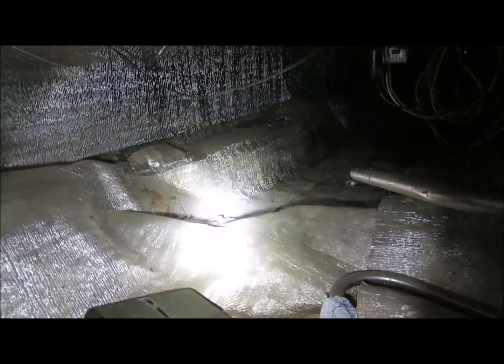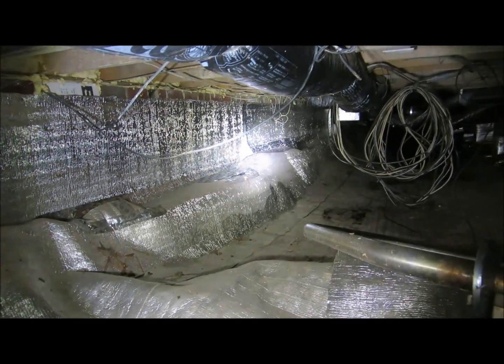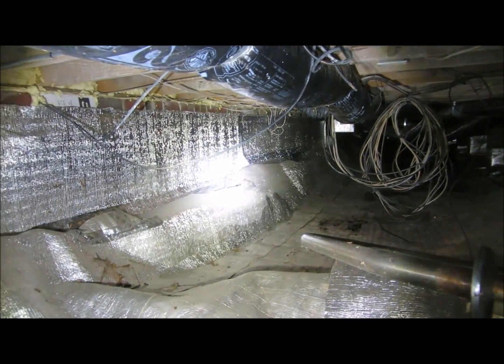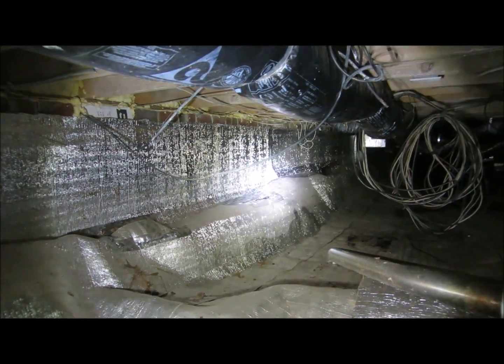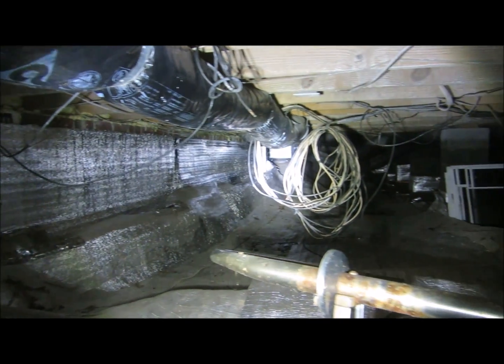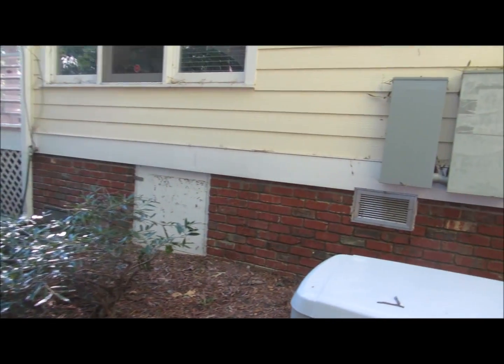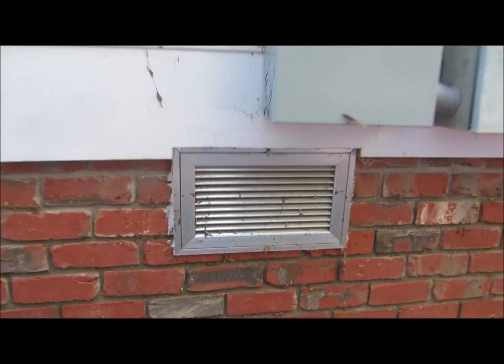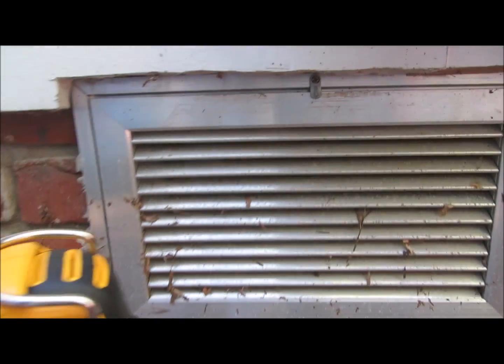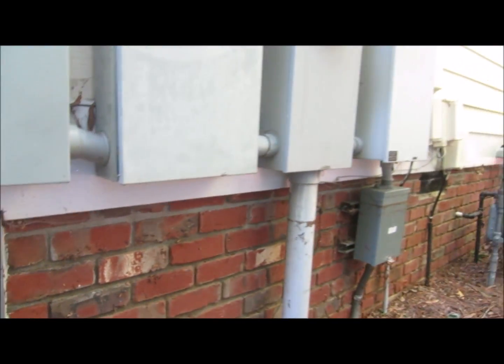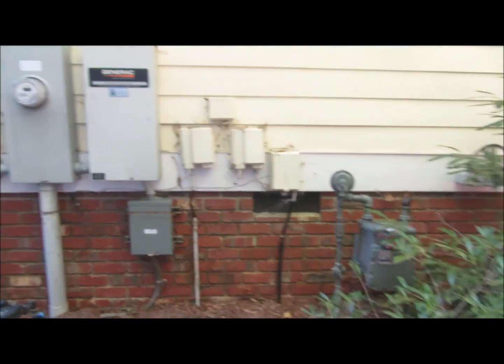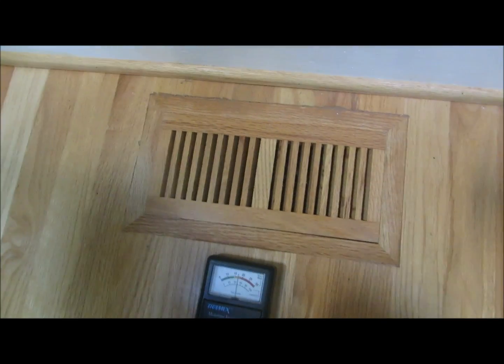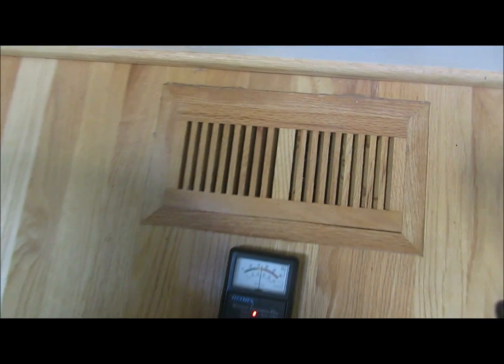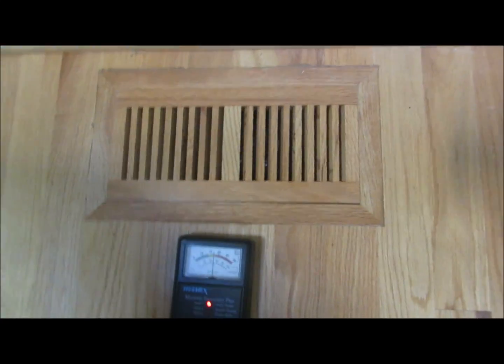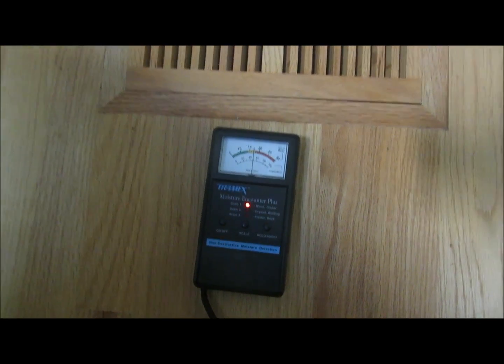All this bubbling of the liner is because water had risen above it. Apparently the flood vents did work. The flood line came all the way up to the middle of this fresh air intake. So right here across the top, you can see the very distinct water line that submerged the generator. These wood registers right now are swollen, so they won't come up. Moisture content is coming in at almost 18%.